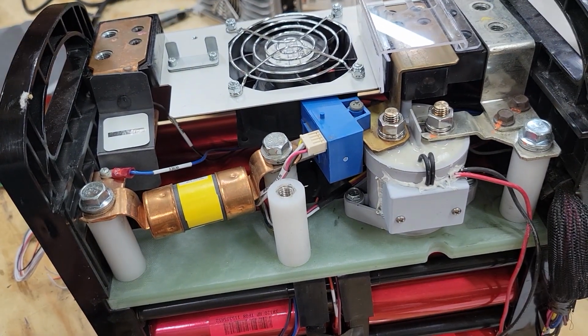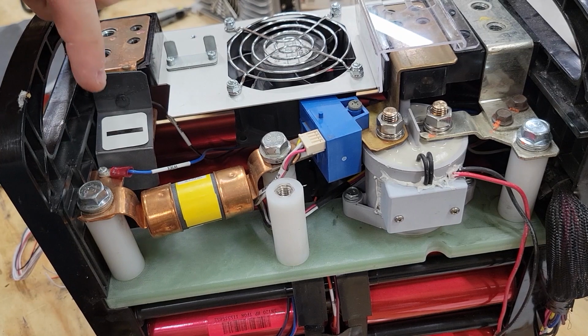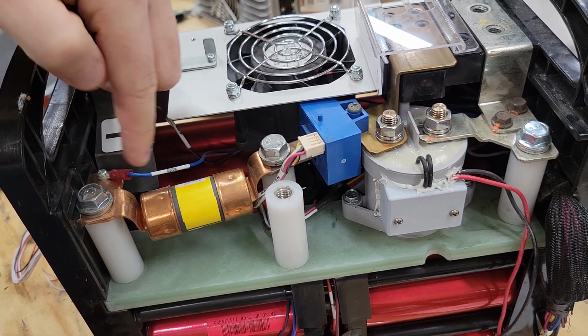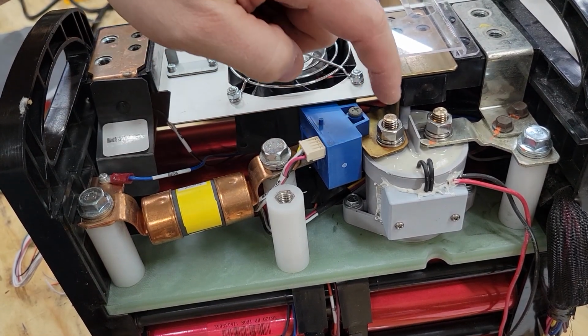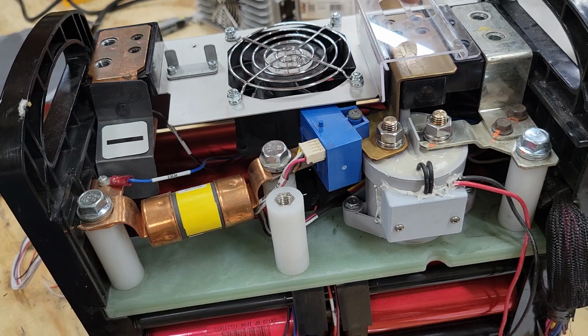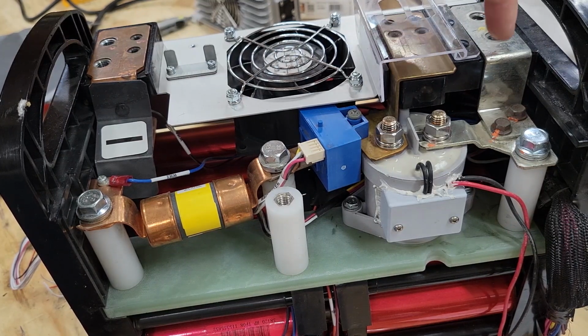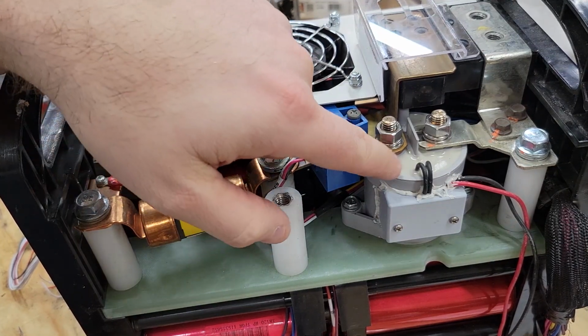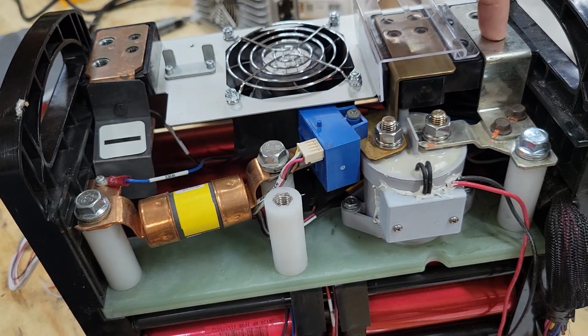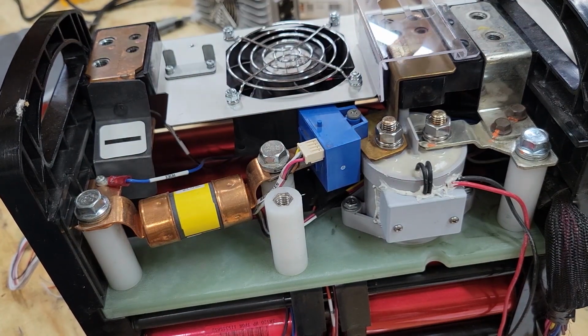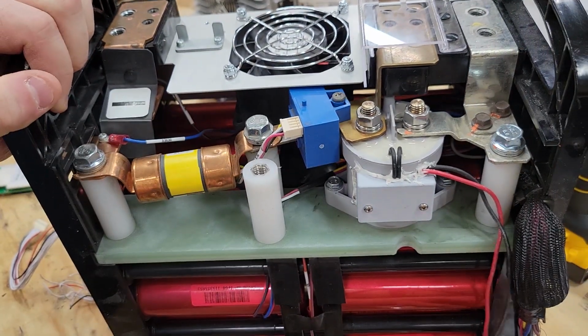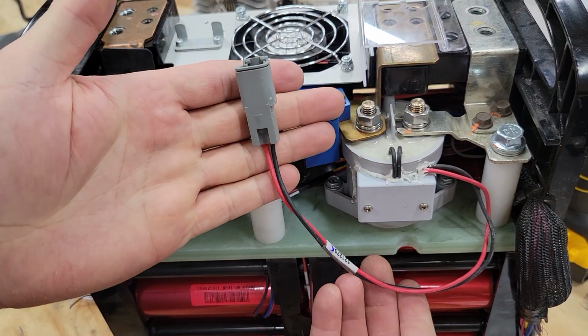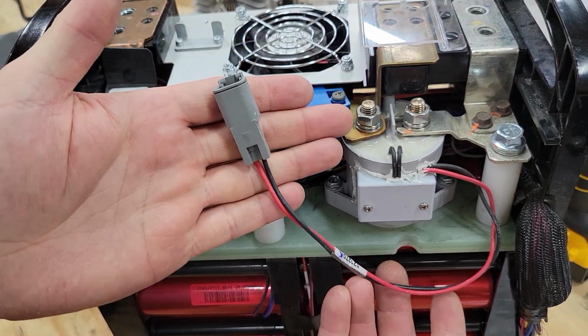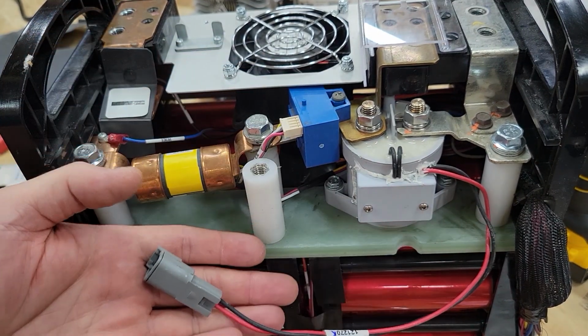So up here we've got our constant negative, and then we've got our positive coming up, fuse, current transformer, and then over here this is constant positive power, and then this one is the relay, the contactor here is controlling this output. So this one's currently dead. It would need power. This is the end of that. So there's no power being delivered to the relay currently.